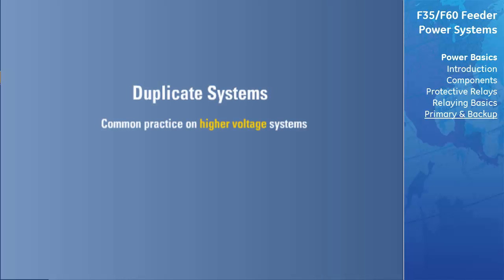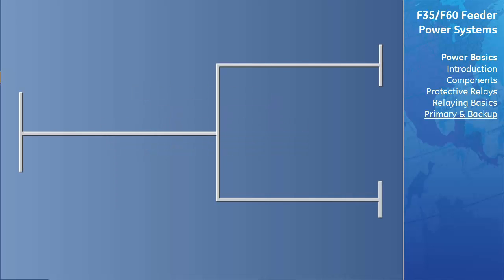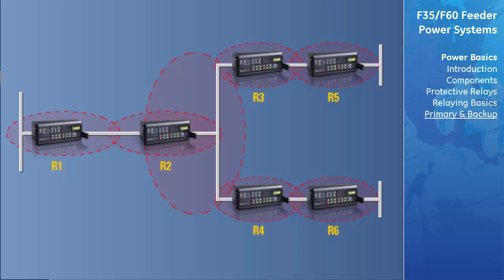On high-voltage systems, it is common practice to duplicate the protection systems to ensure proper operation if a failure occurs. In some cases only the relays are duplicated, while in other cases the entire protection system is duplicated — the preferred choice when economically justifiable. Let's take a look at several backup strategies within one power system transmission line. Relays R1 through R6 are the primary relaying, the D group of relays is the duplicate system, and the L group is the local backup relaying.